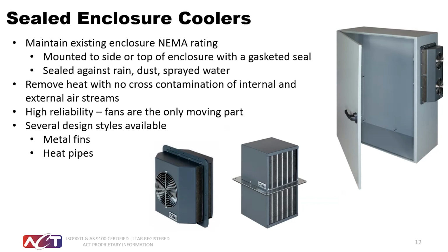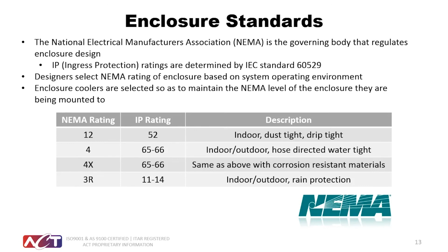By now you have heard NEMA ratings mentioned several times in reference to enclosures and enclosure coolers. These standards are put in place by the National Electrical Manufacturers Association and correspond to the level of protection offered by a cabinet. For example, a NEMA 12 cabinet is intended for indoor use and protects against dust and dripping liquid, while a NEMA 4 cabinet is able to be placed outdoors and can handle washdown from a hose without allowing water into the enclosure. Another rating that is commonly seen is the Ingress Protection, or IP rating, that is governed by the International Electrotechnical Commission and can be cross-referenced to a NEMA rating.